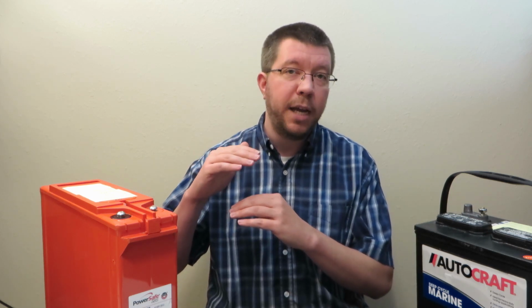Likewise, on the top end, the BMS may not allow you to charge the cells to that higher voltage. Even so, it's best to set your charge voltage low enough so that you avoid that. To greatly prolong your lithium battery life, it's best to set the charge float voltage to slightly below what the manufacturer recommends. And in this analysis, we're going to assume that the bottom 20% of the battery is not being used and that the top 20% is not being used. We'll also assume that the top 20% is not included in the battery spec.